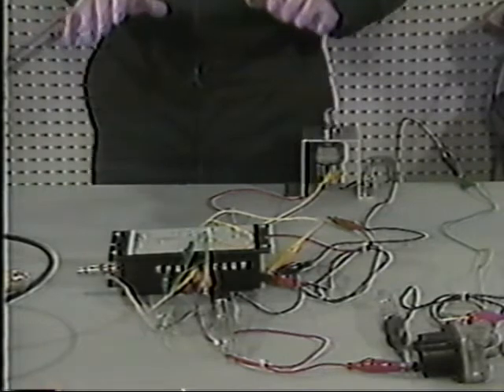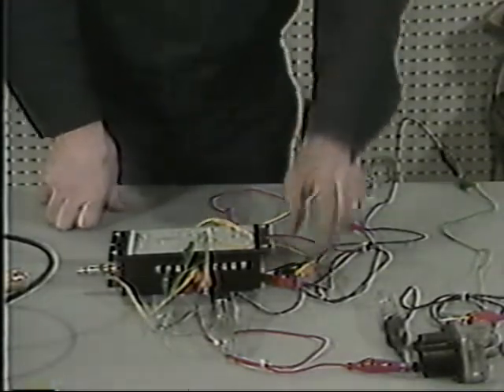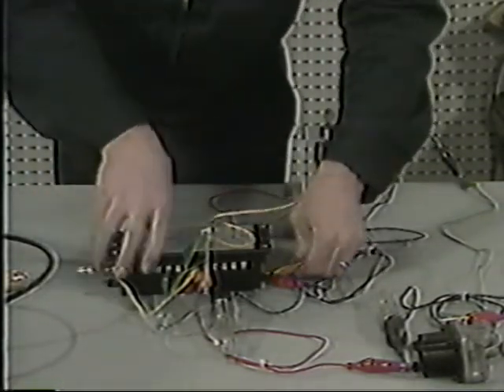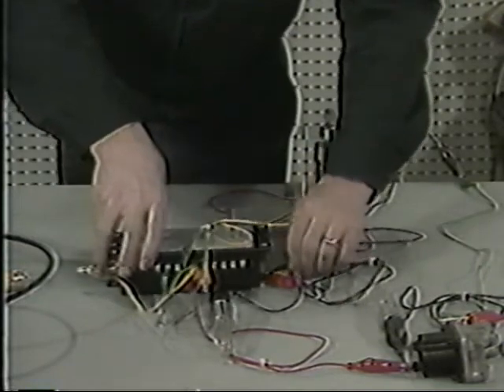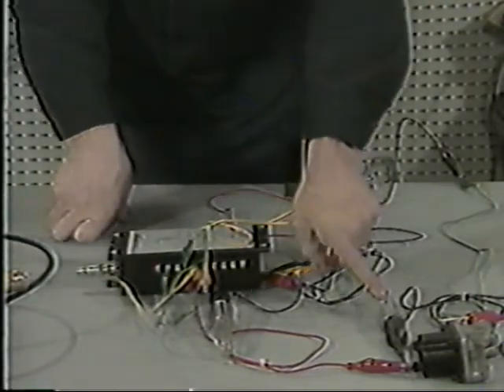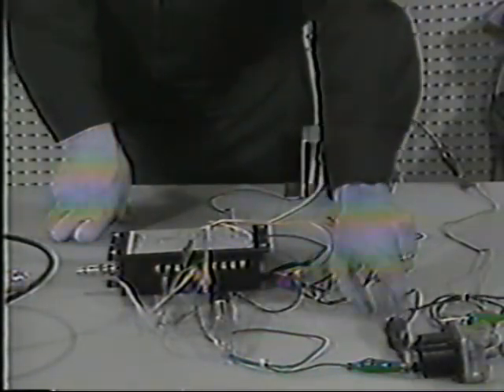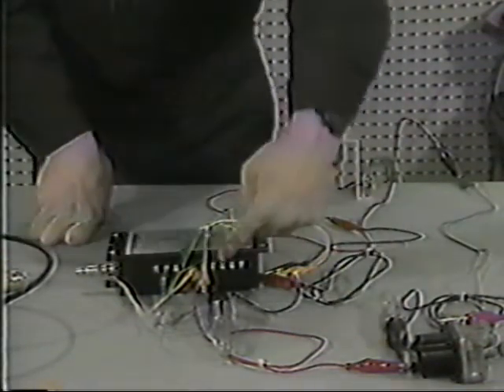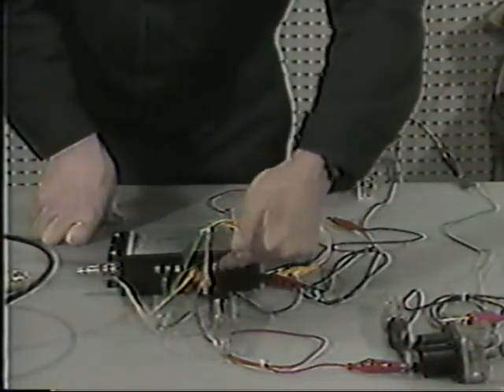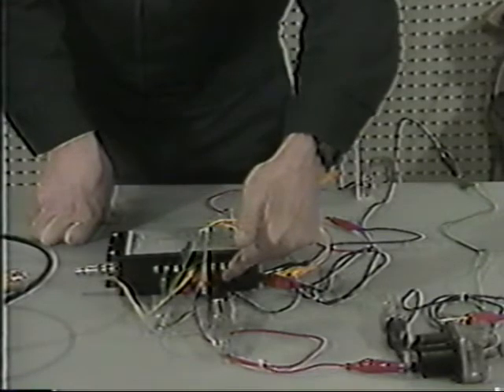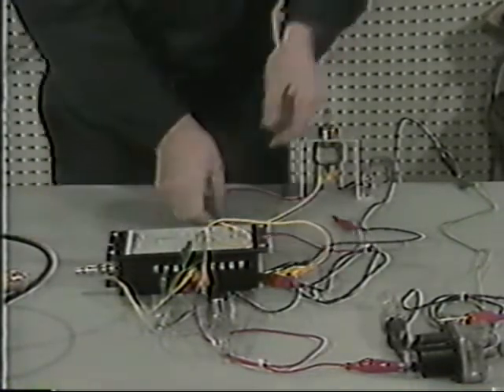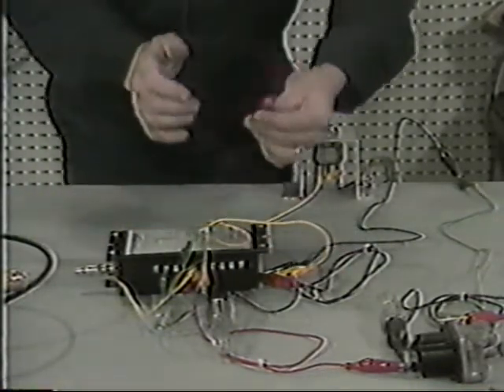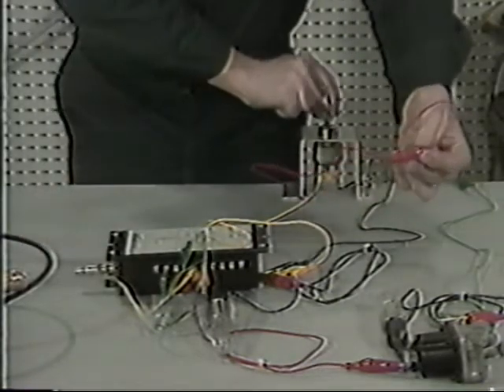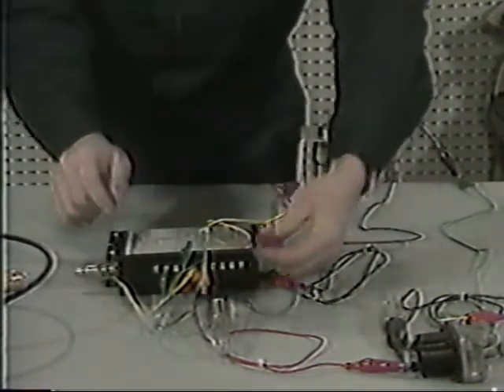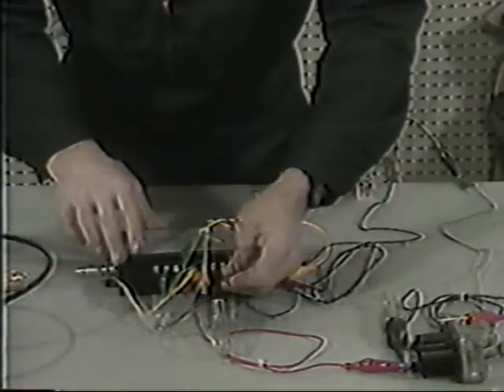All right, at this point we should have no voltage at the test load fuel solenoid, shown by the fact that the test light is off, and we should have no voltage at this test light, which is simulating the warning light on the shutdown system. Make a final connection, which is a key switch controlled voltage wire, to the key terminal on the module, which is number 2.